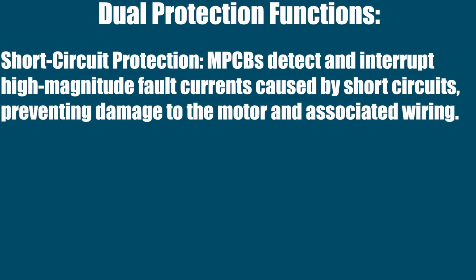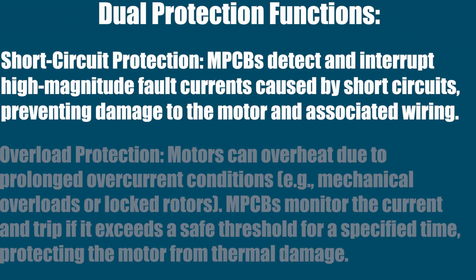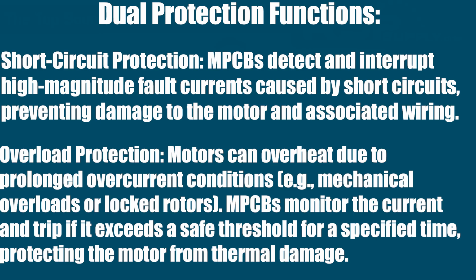Dual protection functions. So there's short circuit protection. Motor protection circuit breakers detect and interrupt high magnitude fault currents that are caused by short circuits, and this prevents damage to the motor and its associated wiring. They also provide overload protection, because motors can overheat due to prolonged overcurrent conditions, like mechanical overloads or locked rotors. MPCBs monitor the current and trip if it exceeds a safe threshold for a specified time. This protects the motor from thermal damage.